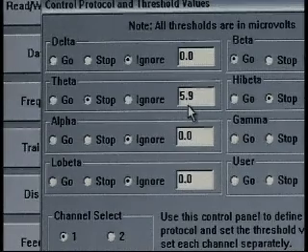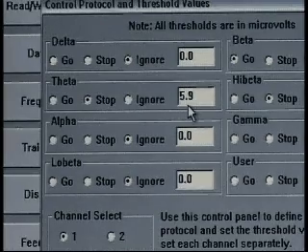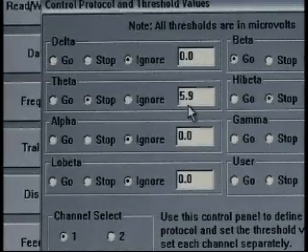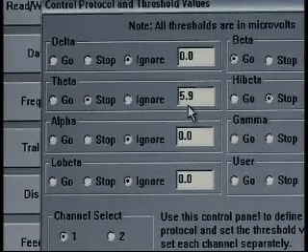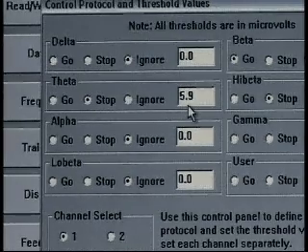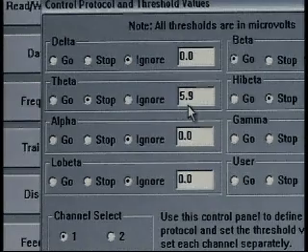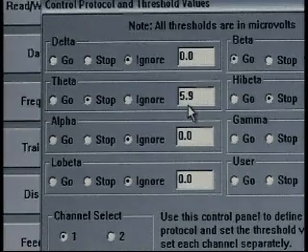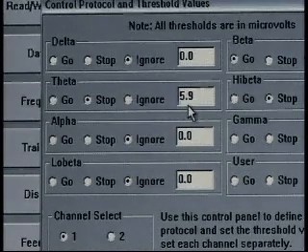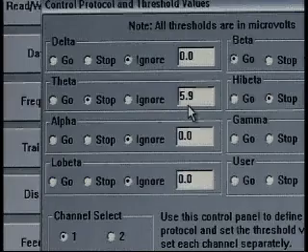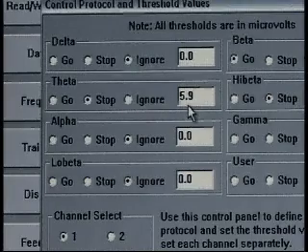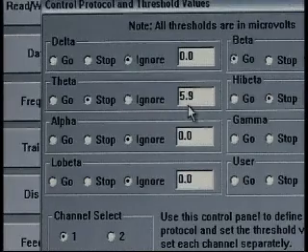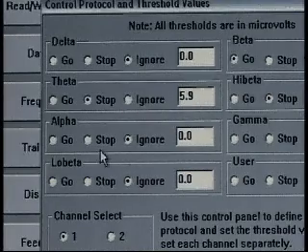Of the last session, or just a default number to start at. The system will, with auto thresholding, reset this number once we begin, so it's not really that important. But to keep in mind, if this is session number two or three or four of the client, that would give you an idea of where the threshold was when the last session ended.